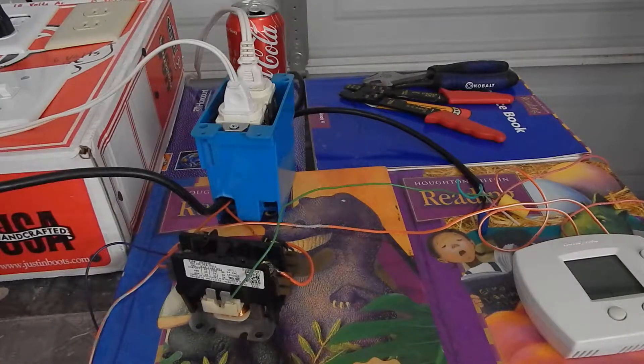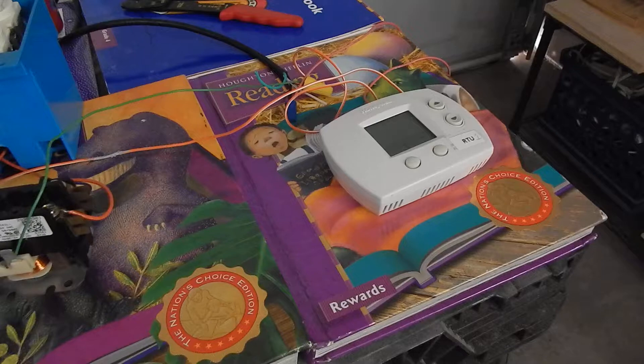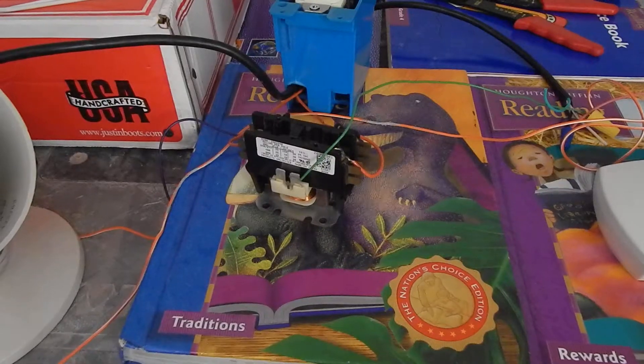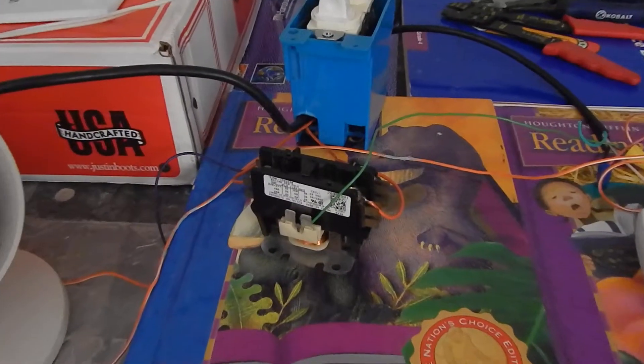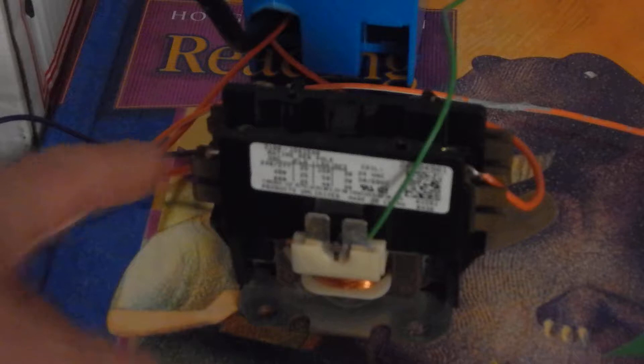Hello YouTubers, today I'm going to show you how to hook a contactor to a thermostat, just like your household thermostat or one like this. Any household thermostat works just fine with this contactor. Right here I have a contactor, and you can see these two little wires coming out this side here — this guy and this guy — that looks like a receptacle acting like a switch.